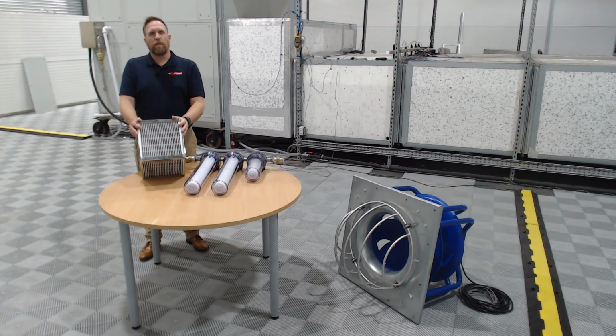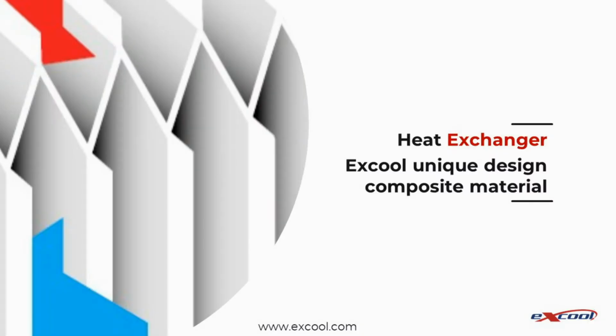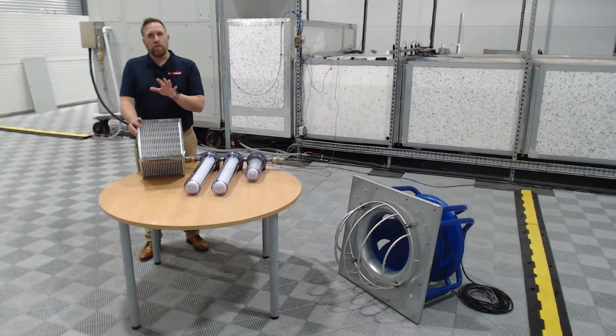The Excool Zero heat exchanger is a result of a decade of R&D that's led to the evolution of the Excool Zero's new and unique heat exchanger design. This has a more compact airflow pattern, it results in a more compact unit, shortening the footprint, it has a lower capital cost, and it has a faster production time. The heat exchanger is manufactured from a non-metallic, non-corroding material for longevity and to ensure the separation of indoor and outdoor air streams, which is a critical part of all indirect evaporative systems.